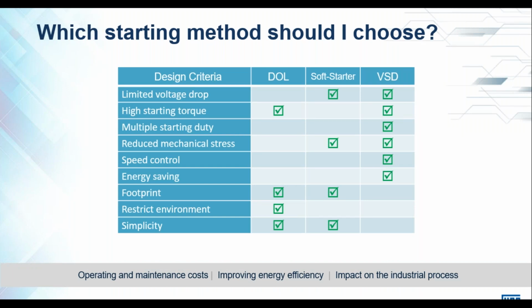Right, I've just put a summary, which again is not something I'm going to spend a lot of detail on. Most people know this. It's just some design criteria compared to which starting method is the optimal to choose for a certain situation. For example, if I need a high starting torque, I would either go direct online or VSD start. Of course, a soft starter is not going to give me a high starting torque. If I need speed control, obviously my only option there would be a VSD. Of course, there are alternatives using a wound rotor induction motor with fixed brushes, but this is just to simplify these three main starting methods.